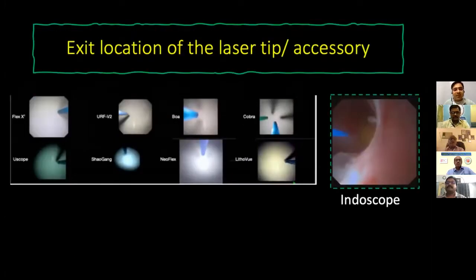Exit location of the laser tip. Exit location of the laser tip is a very important thing. The laser fiber tip can commonly exit at 3 o'clock or 9 o'clock, but in a few disposable scopes, it can also be seen at 12 o'clock. Unlike the Uscope and the LithoVue, which have an exit at 3 o'clock, the Indoscope has a laser exit at 9 o'clock. So I repeat, the exit of the laser fiber of the Indoscope is at 9 o'clock.